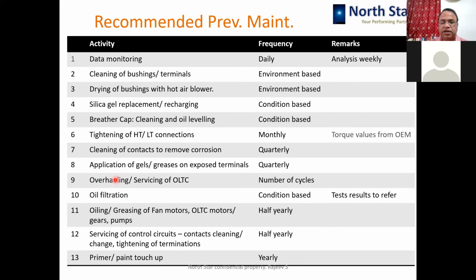Silica gel replacement and charging is condition based. Breather cup cleaning and oil leveling is a very small activity but important activity. It is again condition based. Tightening of HT and LT connections is to be done monthly, and it is to be done against the torque range. Torque values you should get from your OEM, and follow those torque values and keep your connections tightened at those torques only.